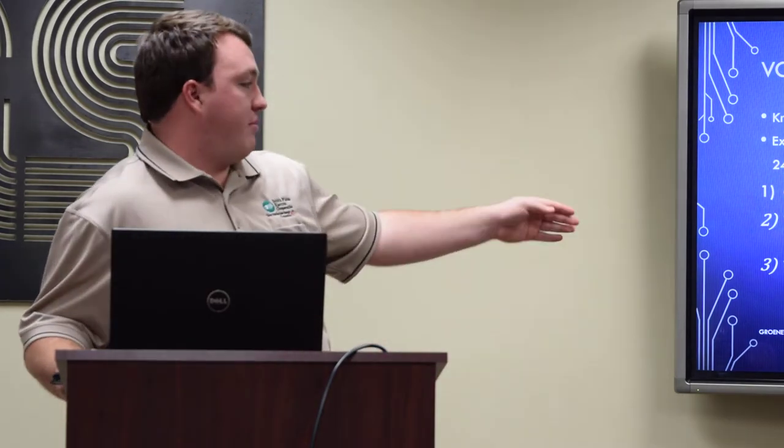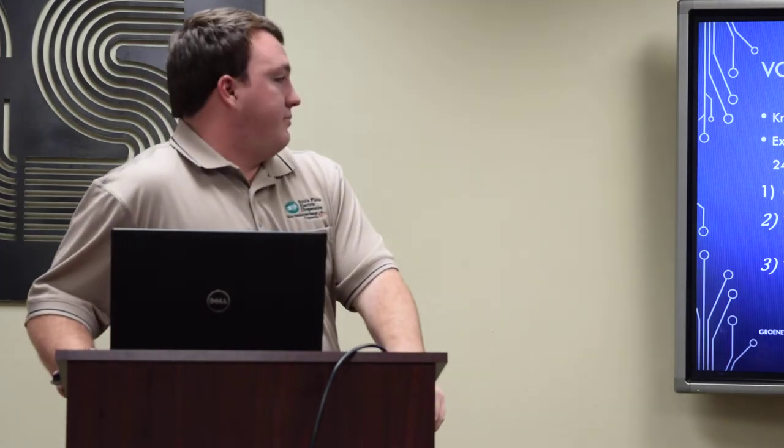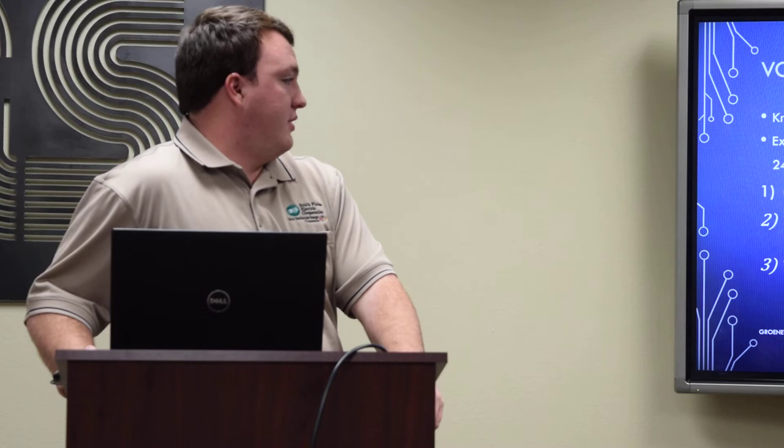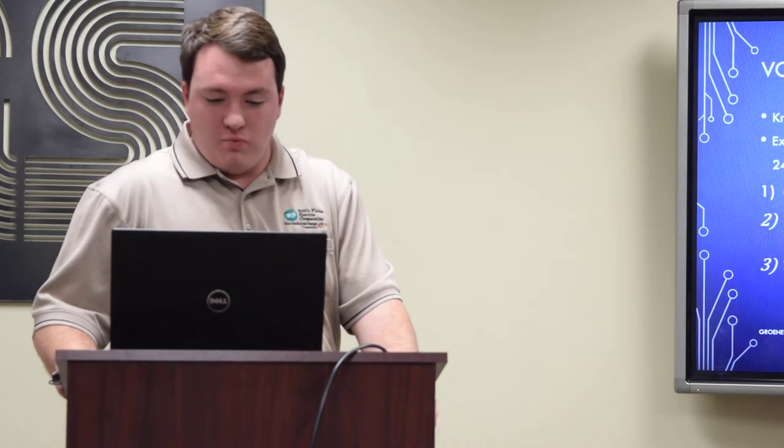I highlight that because at SPEC, we don't do anything if it's above 3% voltage drop. Alan might know more about that. For NESC it's 6%, but we do 3% here. The official code's 5%, but we try to stay under 3%. In this example, where you get 4.8%, it wouldn't work for us. We would find another way to do it, either go overhead some more, or try to run it a different way, upgrade the wire size or something bigger.